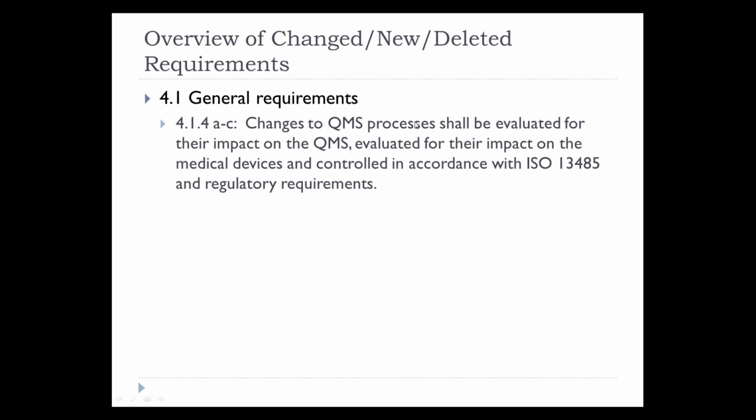4.1.4A through C states that changes to QMS processes shall be evaluated for their impact on the quality management system, evaluated for their impact on the medical device, and controlled in accordance with 13485 and regulatory requirements. So if you're changing a process, you need to evaluate how it impacts your QMS overall and how it impacts any of the medical devices. There's certainly maybe some changes that don't impact the medical device at all.